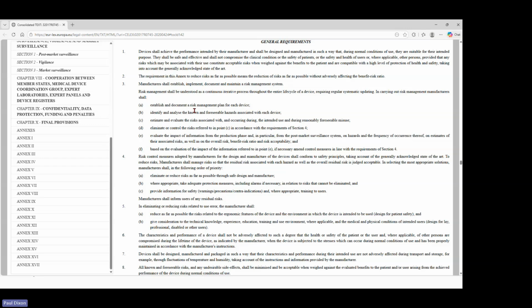Generally speaking, the GSPRs within this section are not applicable to a particular standard for a medical device, because particular standards are generally type tested, and these are GSPRs that relate to the manufacturer's processes. But they are, for example, very relevant to the harmonization of ISO 14971 for risk management, and ISO 13485 for design and manufacturing quality systems.